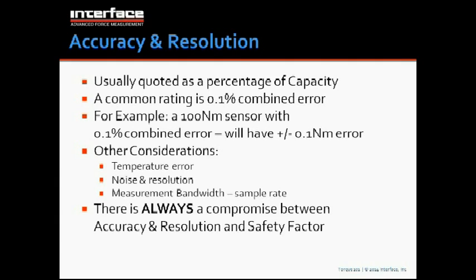Temperature error can be important or inconsequential. If you have a test where you're going to be seeing large temperature shifts during the testing, temperature compensation of the sensor and the temperature specification is very important. Noise and resolution: if you have a lot of noise, you can have some trouble making the measurement even if the sensor is quite accurate. And so that has to do with the instrumentation possibly attached to the sensor, and environmental noise. So noise can be a limiting factor, and that can be a little hard to pin down.